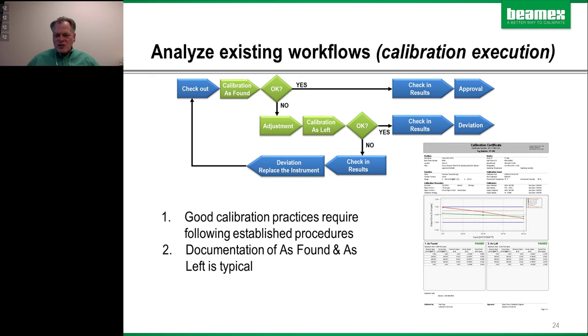So these are kind of things you should look at in your program and look for efficiency gains. And as Chuck said, you need to establish procedures and follow those procedures. And doing good documentation is important. I know you can't see this document, but you've got database information, you've got event information, procedural information. This is traceability, what was used to make the measurement. Here's the actual data. Here's a graph. You can see the as found was maybe at an angle and the as left was left perfect, and then who performed the calibration. These are all good examples of proper documentation.